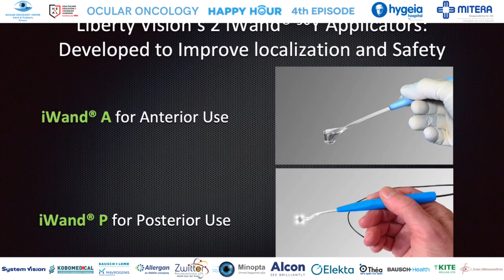Though the FDA has cleared us for 3 sizes, our first LV-Y90 disc is 6 millimeters in diameter. The Y90 is safely encapsulated within its titanium shell. Anterior application is simple. The area of treatment is marked on the eye surface with tissue dye. Then the device is placed according to those markings and held in place for the minute or minutes of treatment.